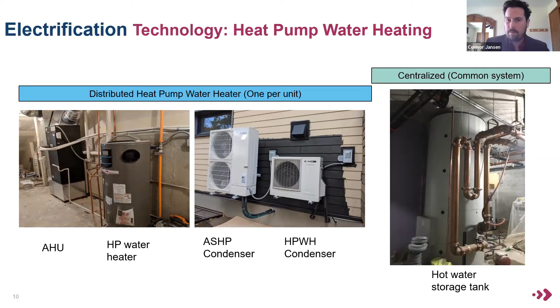So when we talk about heat pumps, one of the first questions that we get is how well do they work in cold weather? And so cold climate heat pumps, which are a specific type of heat pump, can supply really efficient heating and cooling in the Illinois climate. However, we do recommend that backup heating, usually in the form of electric resistance, be provided for sub-zero condition operation, especially in retrofits. And the reason for this is under about 5 degrees Fahrenheit, the heat pump systems tend to lose some heating capacity, and they also have to operate more often in a defrost mode.